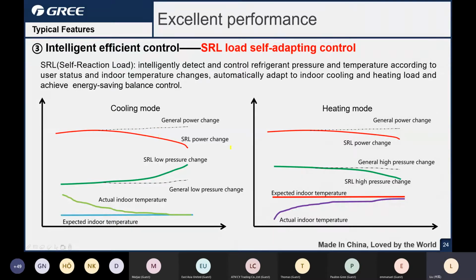Okay, that's for cooling mode. And the heating mode is similar. For cooling mode, SRL controls the low pressure. For the heating mode, it controls the high pressure. It also depends on the actual and the setting temperature. The closer to the reaching point, the bigger the slope will be to reduce the power consumption. Okay, that's the SRL control logic.